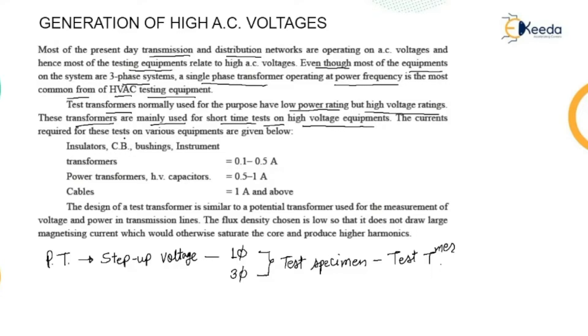The current required for these tests varies by equipment. For insulators, circuit breakers, bushings, instrument transformers, the required current is 0.1 to 0.5 ampere. For power transformers and high voltage capacitors, it is 0.5 to 1 ampere, and for cables it is 1 ampere and above.